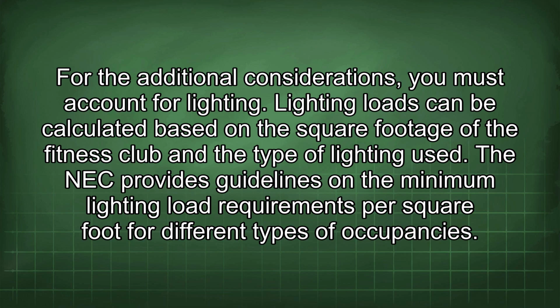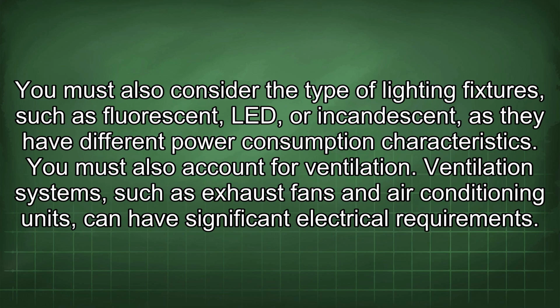For the additional considerations, you must account for lighting. Lighting loads can be calculated based on the square footage of the fitness club and the type of lighting used. The NEC provides guidelines on the minimum lighting load requirements per square foot for different types of occupancies. You must also consider the type of lighting fixtures, such as fluorescent, LED, or incandescent, as they have different power consumption characteristics.